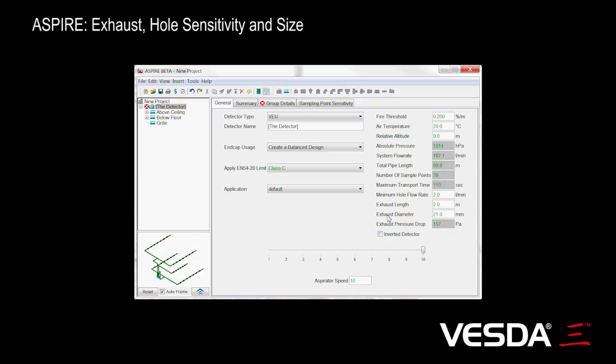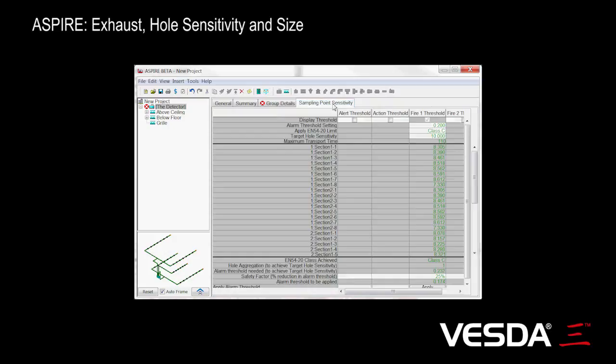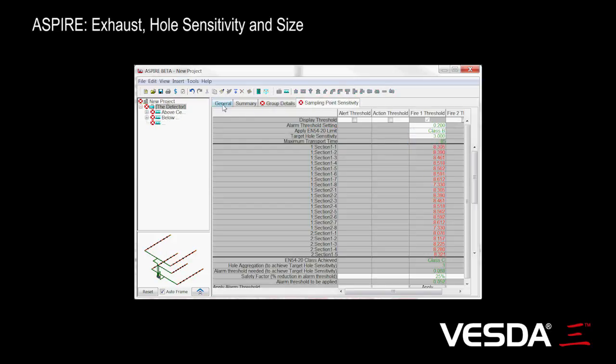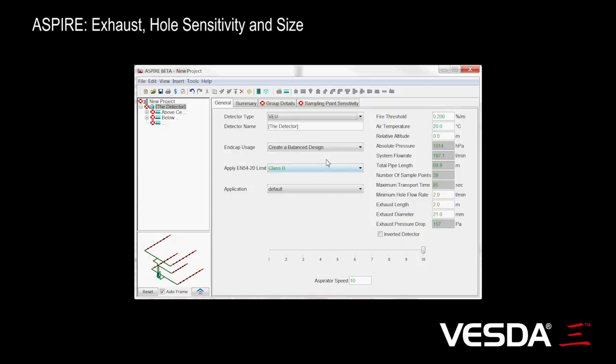One thing I wanted to point out is we now have our EN54 20 limit brought forward to the front page here. We can change it here to say class B. We won't worry about the items going red for the moment. You'll see it's come to class B here, but the other thing to recognize is it also changes the transport time.